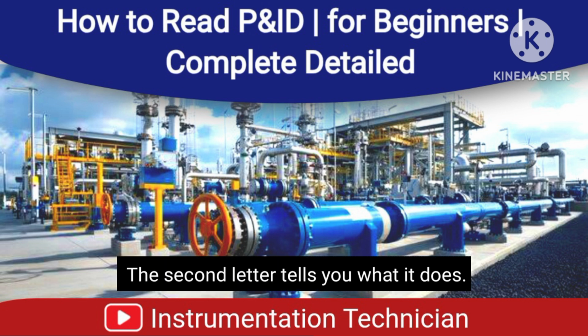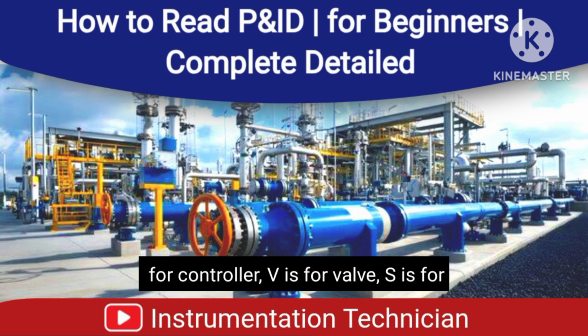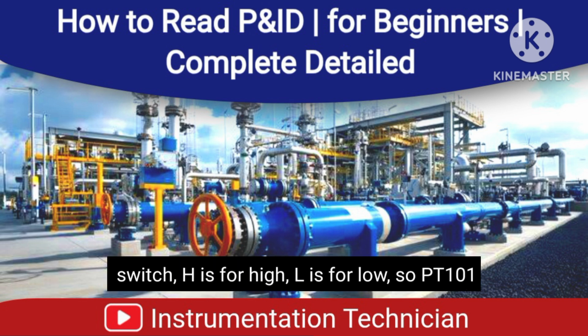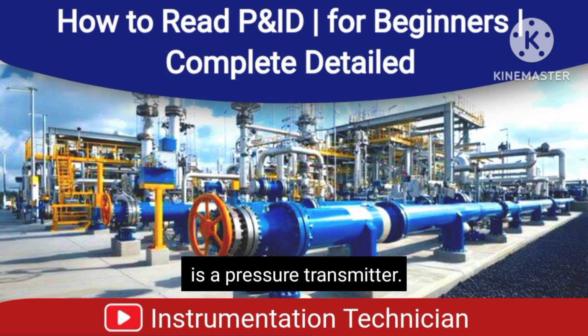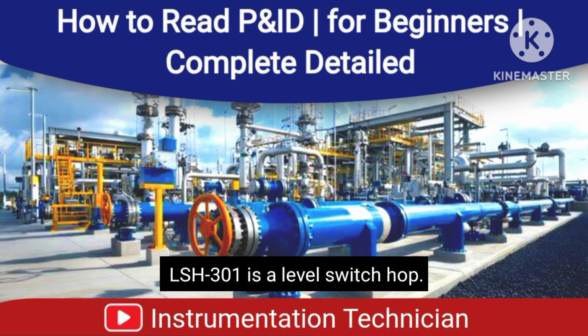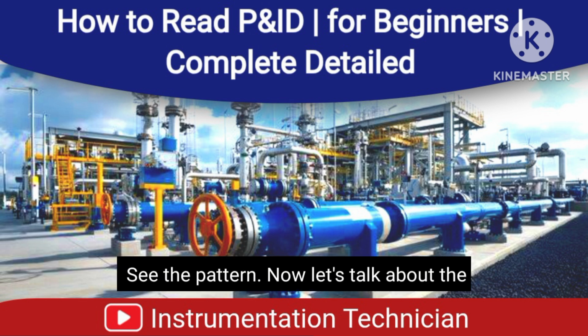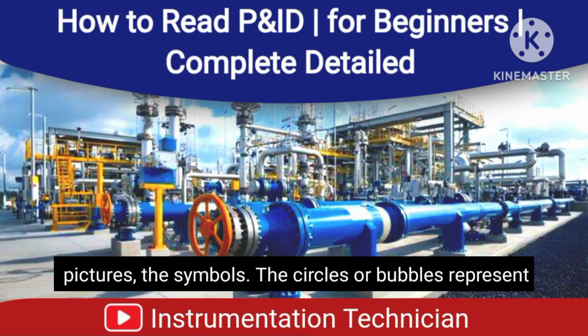The second letter tells you what it does. T is for transmitter, I is for indicator, C is for controller, V is for valve, S is for switch, H is for high, L is for low. So PT101 is a pressure transmitter. LSH301 is a level switch high. See the pattern?